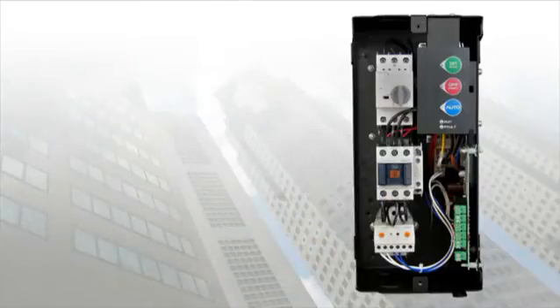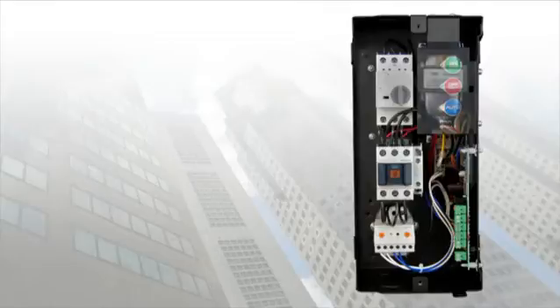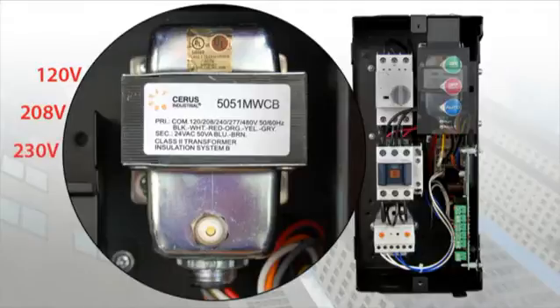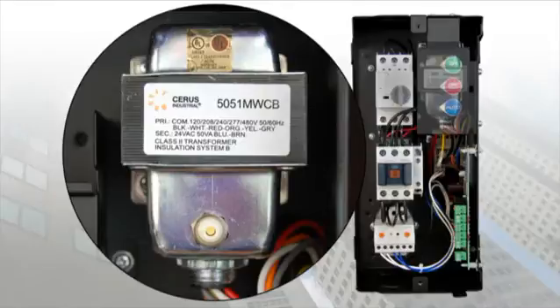For convenience, all of our BAS starters come standard with a multi-tap control power transformer, accepting 120, 208, 230, 277, and 480 volt input with a 24 volt secondary for controls.